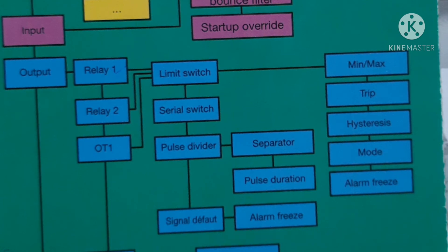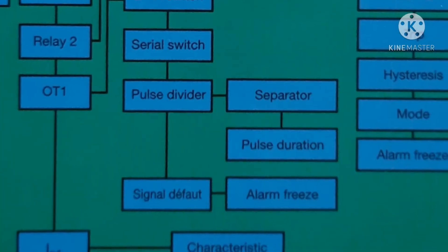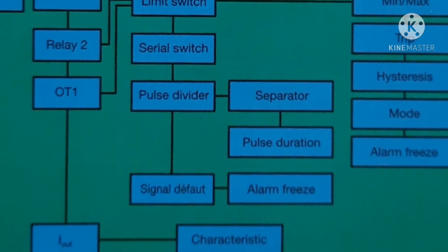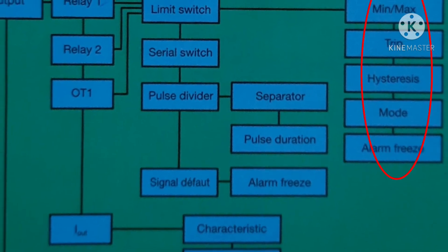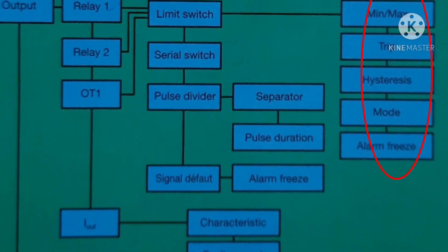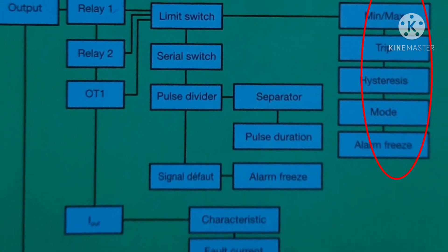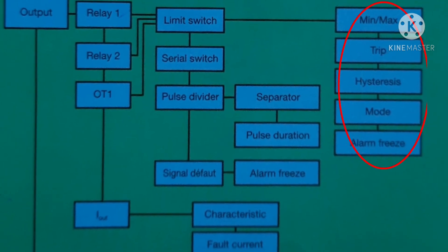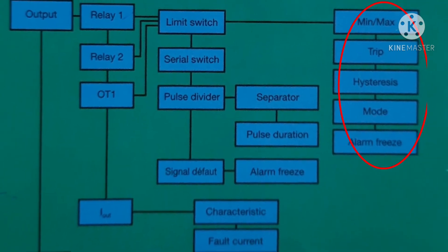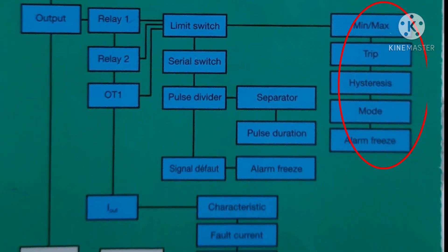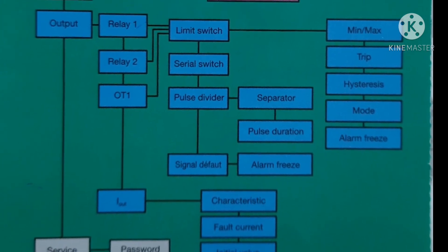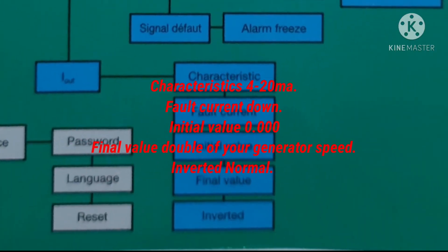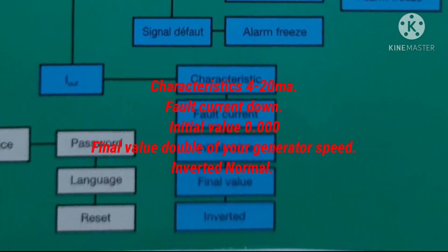Back on relay 2, press the down button for OT 1. Follow the same procedure as the previous program. This time select 'minimum' and write in trip 10% of your generator speed, then in hysteresis write 10% of that 10% of your generator speed. Mode active, alarm freeze off. The rest will be the same as previous. Return, and the last one is I out.